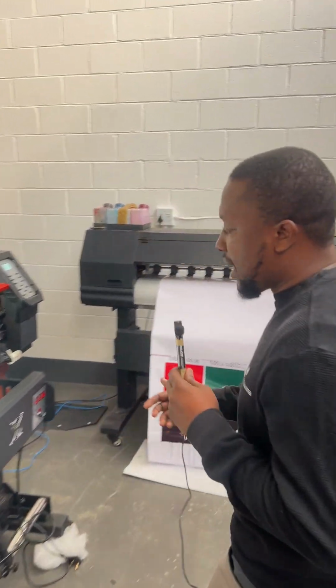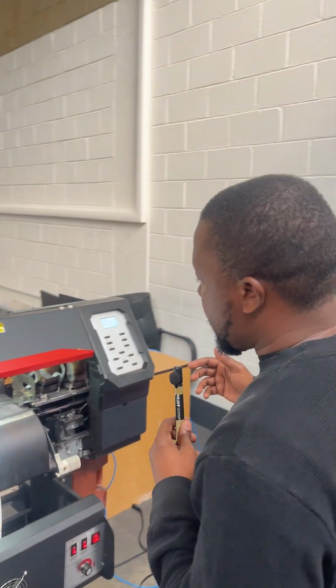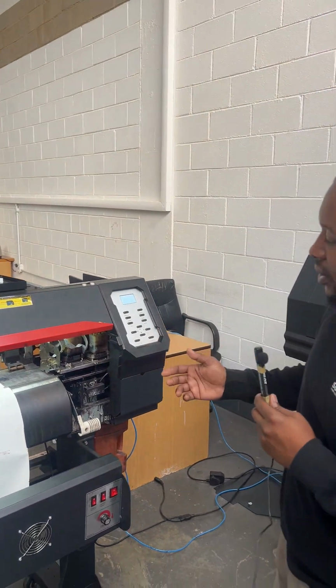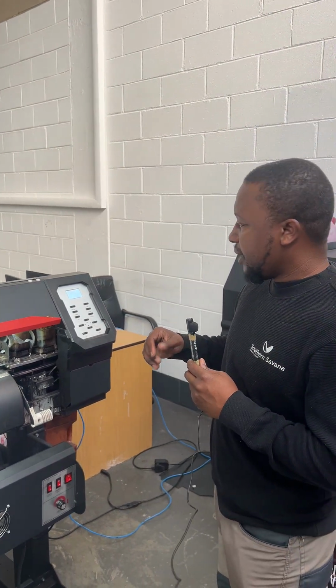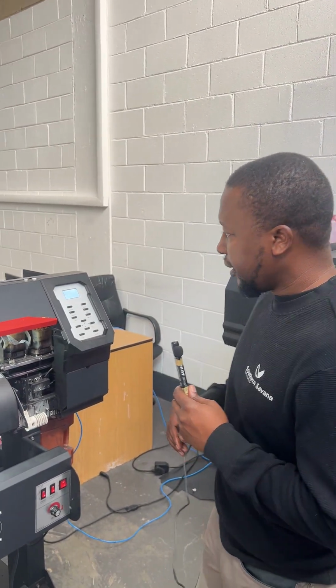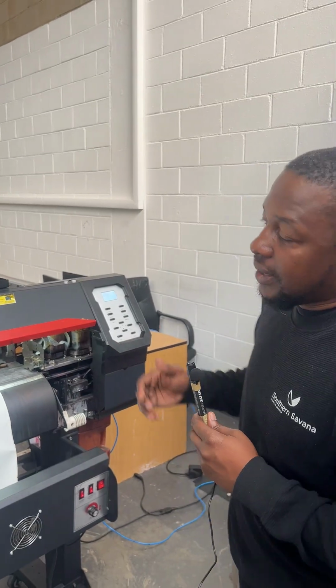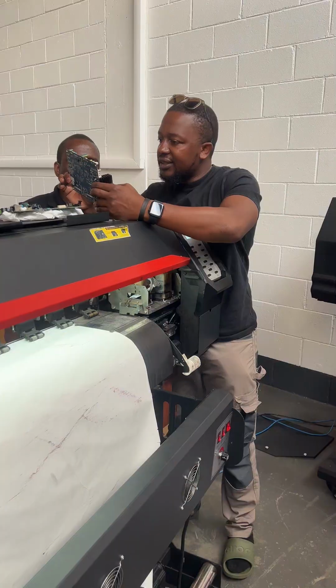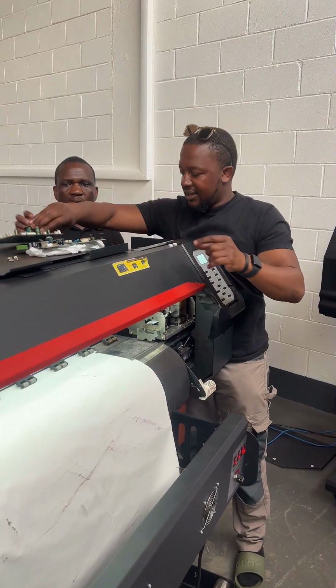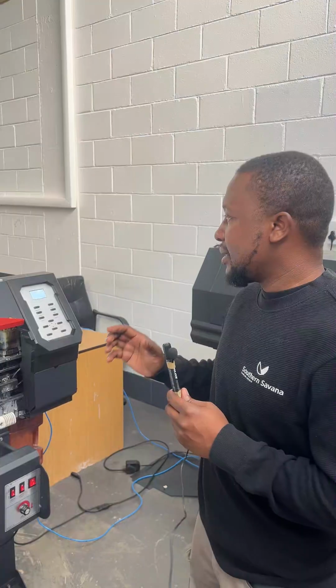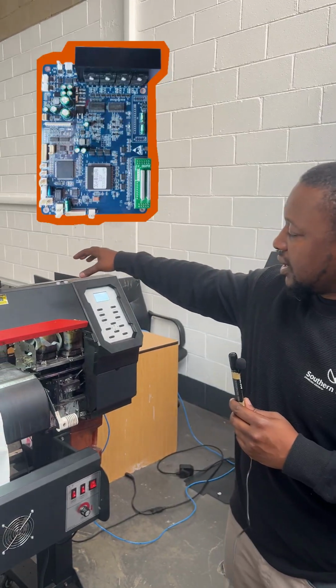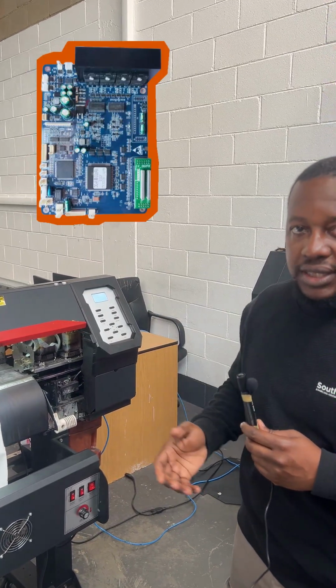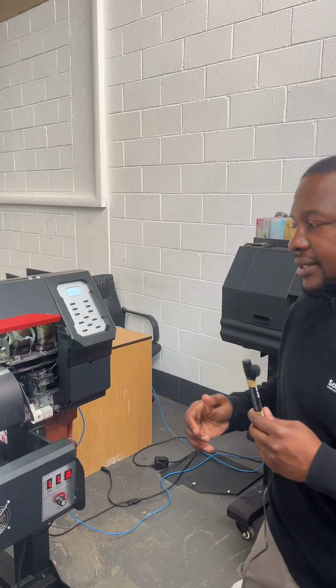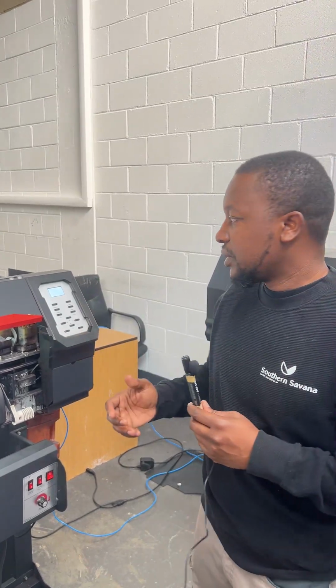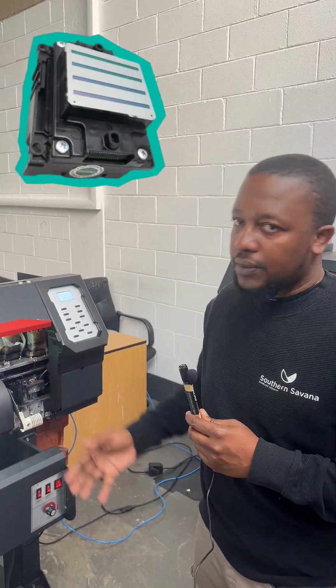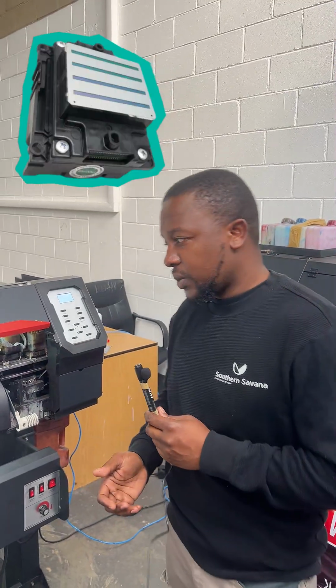Basically, what was happening is the machine was constantly initializing when you switched it on, and eventually gave error code 34. And after it was brought in, obviously our technicians started working on the machine, testing it to try and figure out what's wrong with it. And what we discovered was that the carriage board for this printer was faulty, and that's the part that needs to be replaced. And on top of the carriage board being faulty, the printer heads were also faulty, and those will need to be replaced as well.